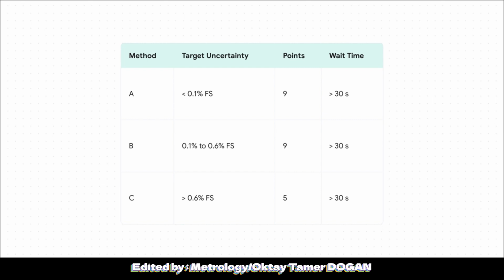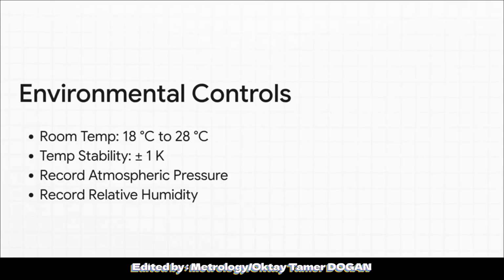It is incredibly rigorous. And that rigor doesn't stop at the procedure itself. It extends right into the environment. Because things like the density of air and the expansion of metals can actually skew the readings, Euramet CG17 demands rigid lab conditions. The room has to be kept between 18 and 28 degrees Celsius, with a temperature stability of plus or minus 1 Kelvin. Furthermore, the lab has to record the exact atmospheric pressure and the relative humidity during the test. Literally every microscopic variable is locked down and controlled.